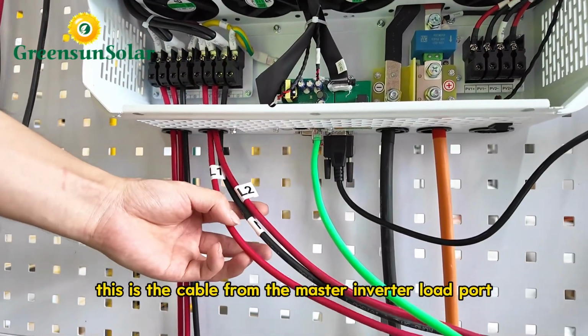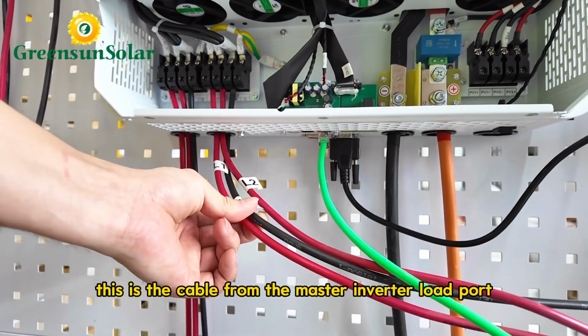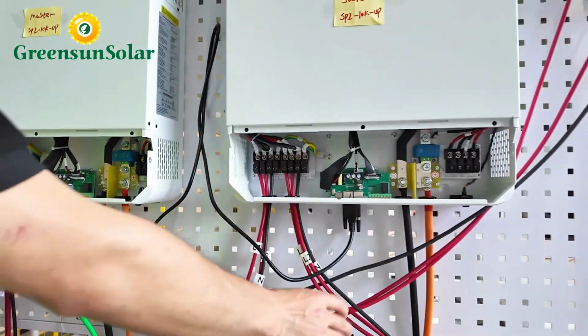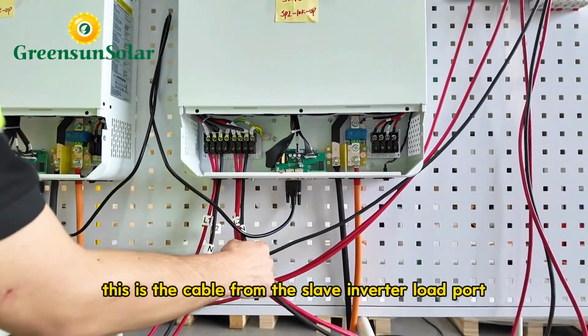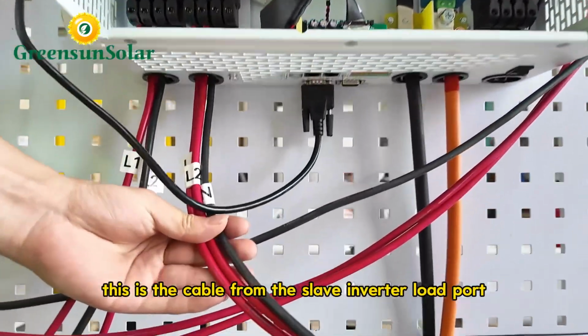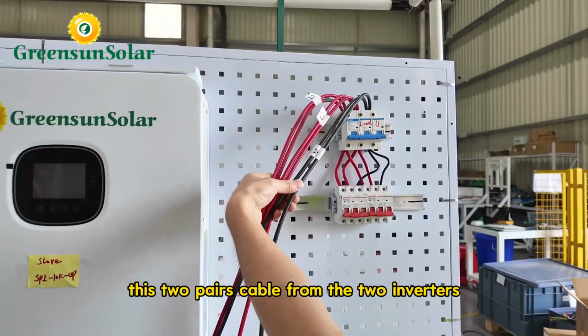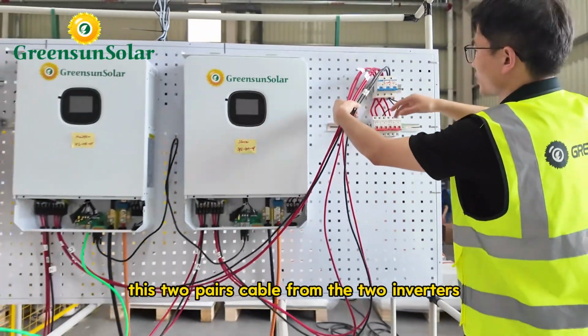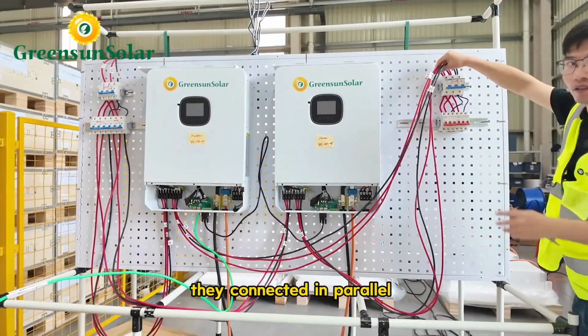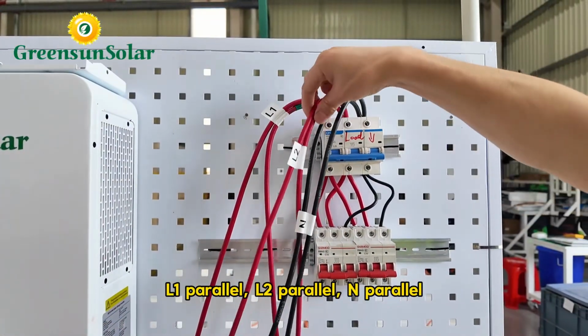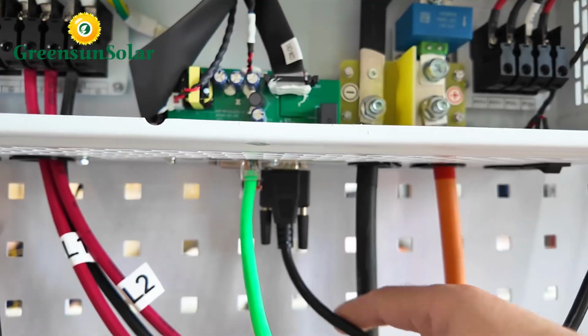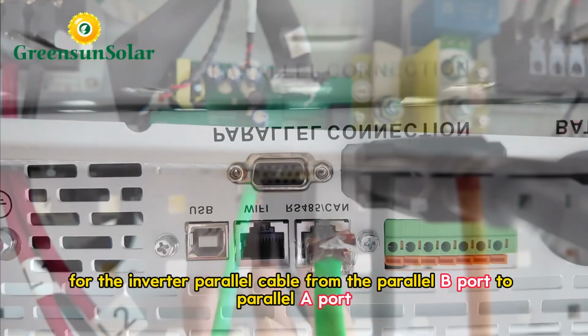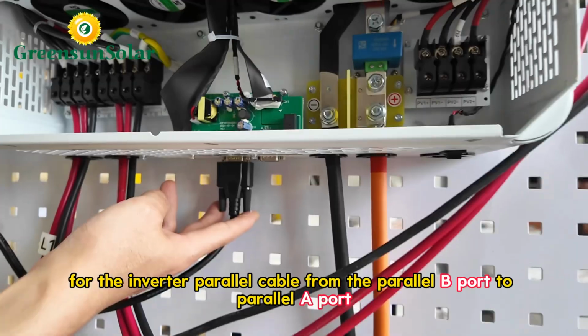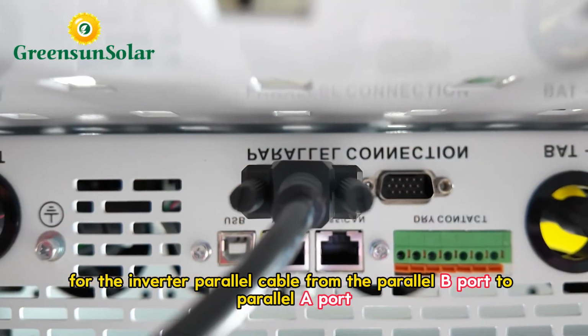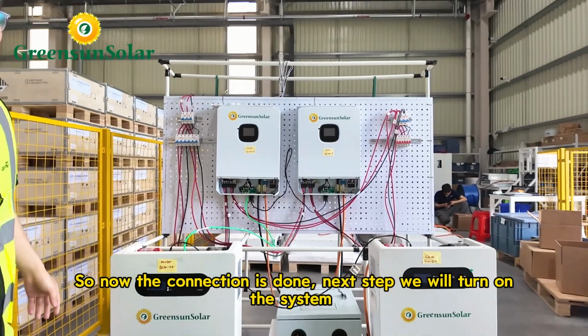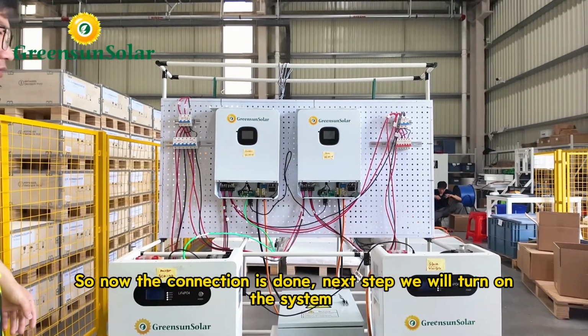This is the cable from the master inverter load port, and this is the cable from the slave inverter load port. These 2 pairs of cables from the 2 inverters are connected in parallel: line 1 parallel, line 2 parallel, neutral parallel. For the inverter parallel cable, connect from the parallel B port to the parallel A port. So now the connection is done. Next step, we will turn on the system.